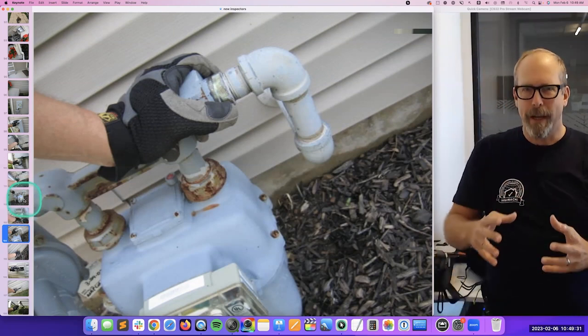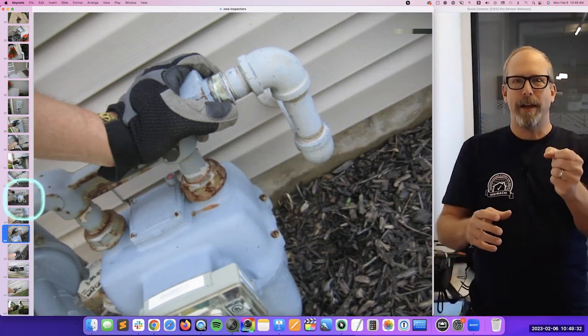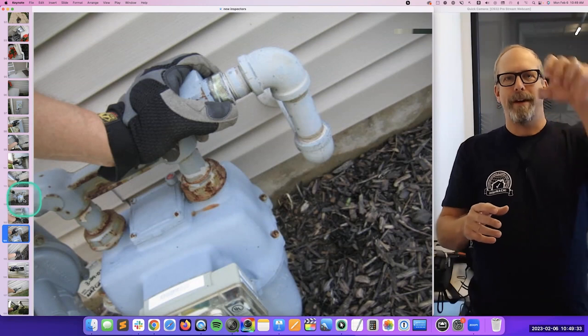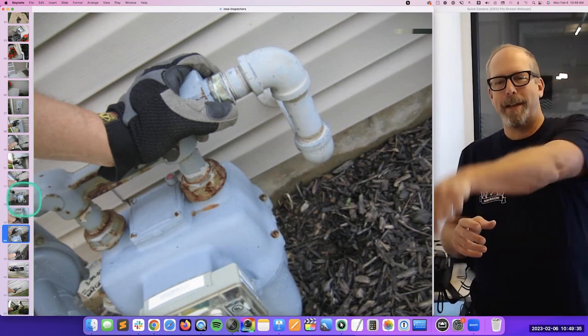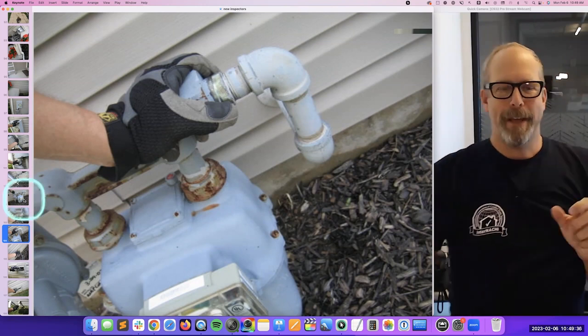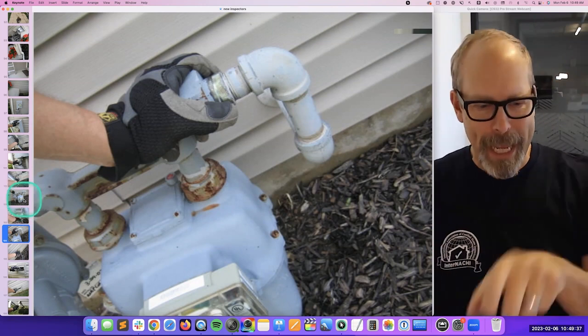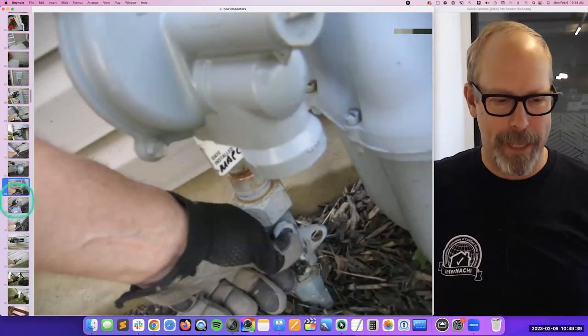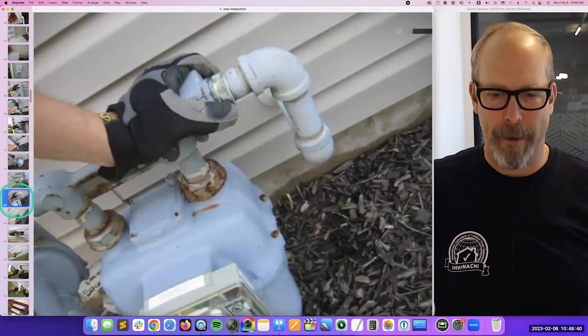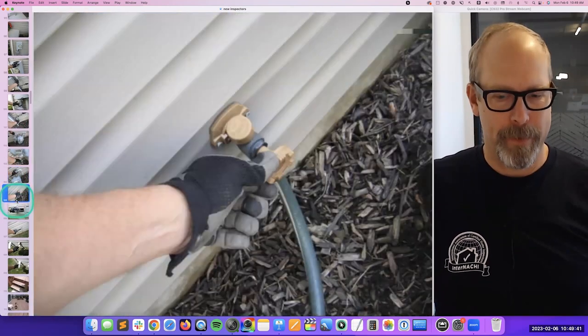There's the gas meter — so I know I have natural gas, not oil, not propane. There's the gas valve regulator — don't worry about surface rust, no big deal — and then it goes into the house with a shutoff valve. You see my hand touching things — that's just a habit of mine. I take a picture of the system, then get close enough to touch every component and take a picture of the component. That forces me to inspect everything, take a picture of everything, and put it in the report. I follow the sequence: gas meter comes up from the ground, goes to the valve, to the pressure regulator, to the meter, and back in the house.